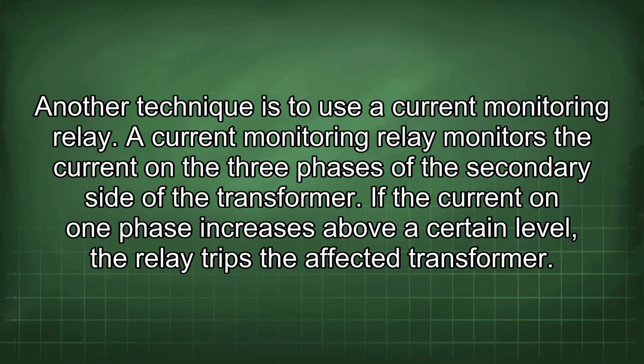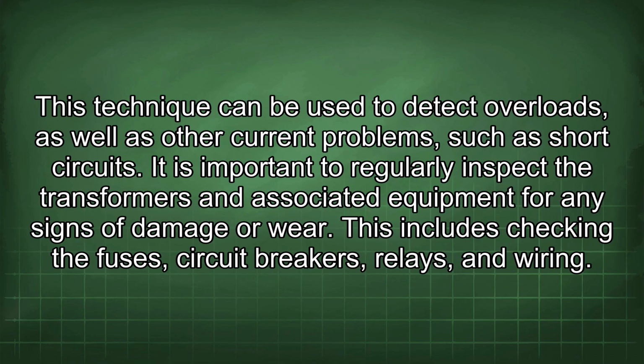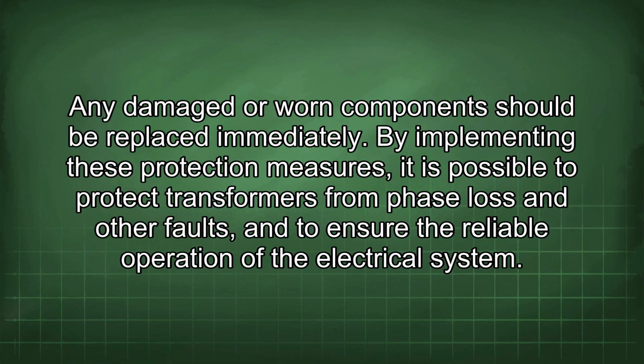If the current on one phase increases above a certain level, the relay trips the affected transformer. This technique can be used to detect overloads, as well as other current problems, such as short circuits. It is important to regularly inspect the transformers and associated equipment for any signs of damage or wear. This includes checking the fuses, circuit breakers, relays, and wiring. Any damaged or worn components should be replaced immediately.